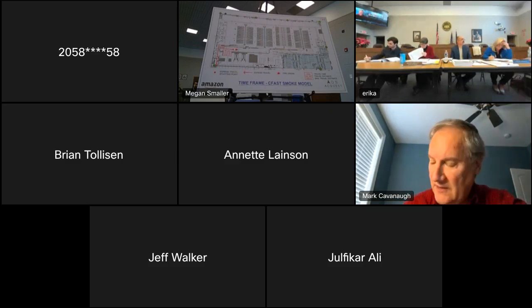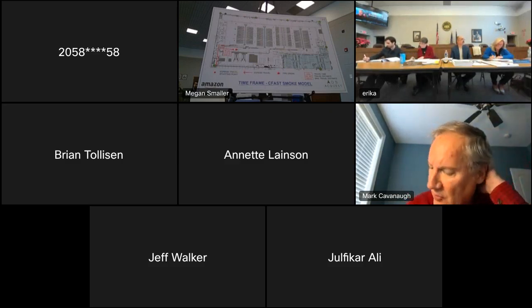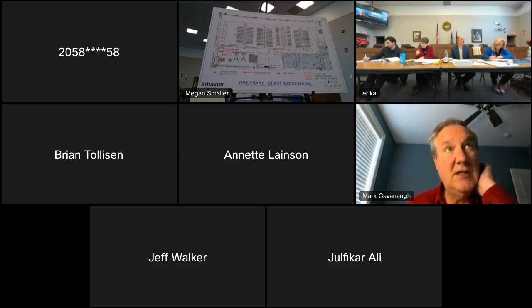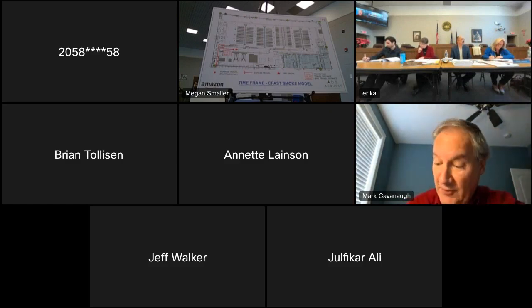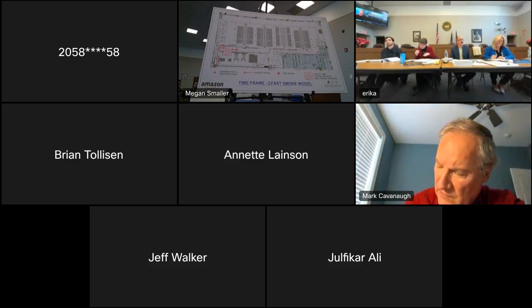The next question I have is on canopy protection. I believe we're going back to NFPA 13 for that protection, so what hazard do we identify for the canopy in this protection? I believe what they're using is a standard upright storage head designed for that use, with a K factor of 12, and of course they're dry sprinkler heads. Correct.